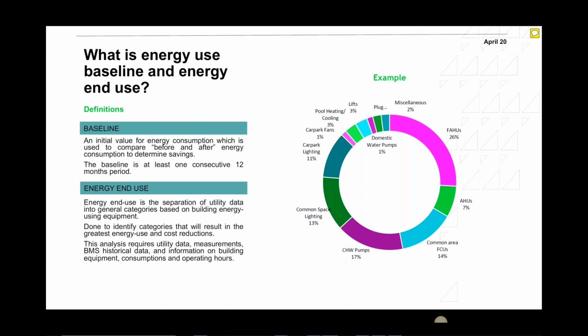Now, what is the energy end use? It's the separation of utility data into general categories based on building energy-using equipment, done to identify categories that result in the greatest energy use and cost reductions. This analysis requires utility data, on-site measurements, BMS historical data if you're lucky enough to find it working and trending, and information on building equipment, consumption, and operating hours. So you rely a lot on what the facility management people tell you.